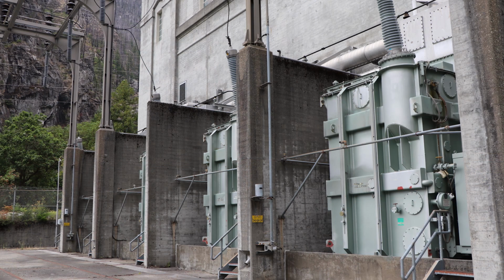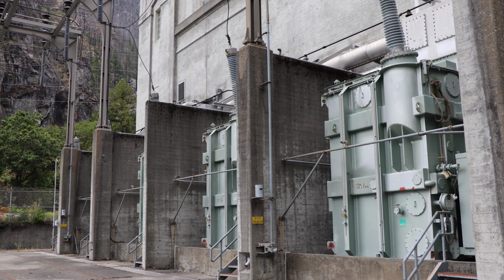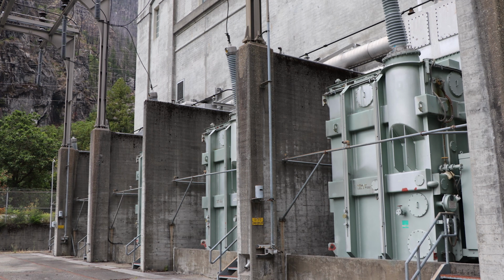Is this similar to speed, no load? Because you're just bringing up free voltage on the line? So speed, no load is your unit is online, it's connected, the breaker's closed to the grid, to the bulk electrical system, but it could be at zero. It is connected, so you can immediately bring it up to whatever megawatt value or power requirement you want. With black start units, you're basically putting the unit online to charge the transmission line with the power you need, then you'll bring it up to whatever megawatt value it demands from there.